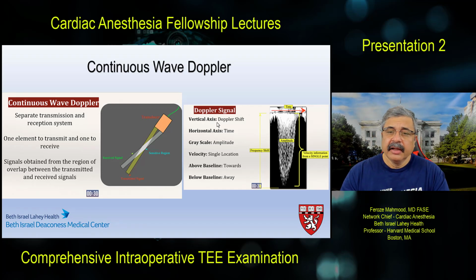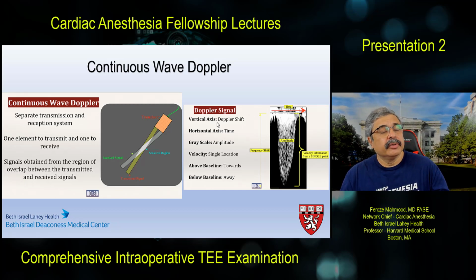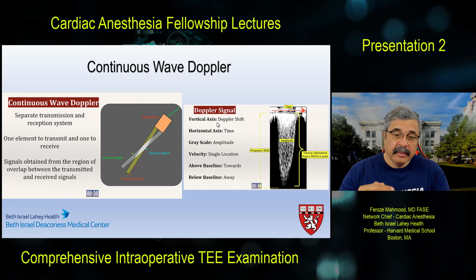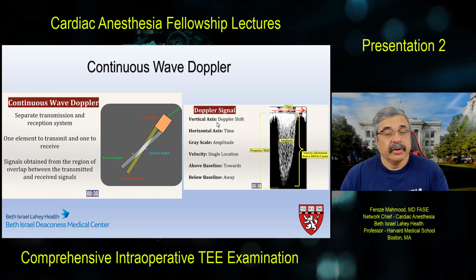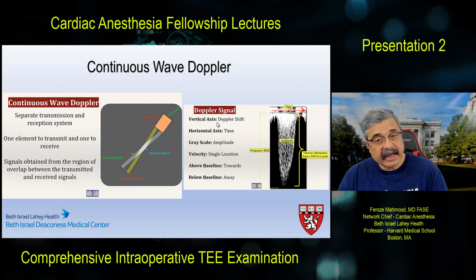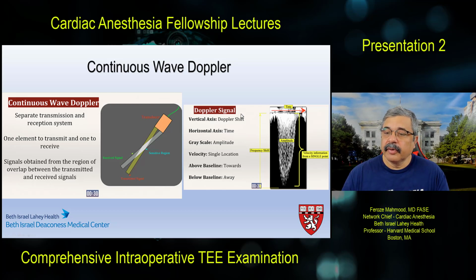Now, as you can imagine, since you are continuously emitting and continuously receiving, there'll be an element of range ambiguity. You'll be able to get the highest velocity in the line of interrogation, but you'll have range ambiguity in not knowing where exactly this Doppler shift is occurring, and therefore all that you receive is the highest velocity because you're receiving all signals that are coming back to you, and you're not time gated, and therefore you cannot really establish where exactly this Doppler shift is occurring.